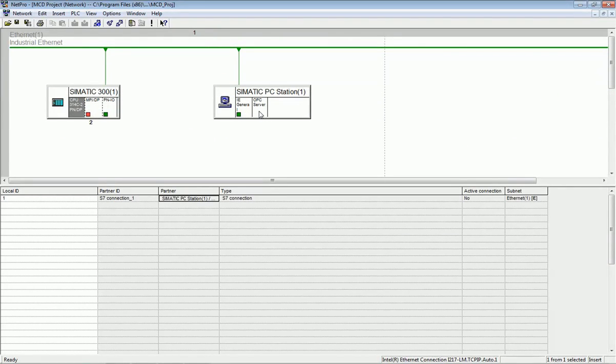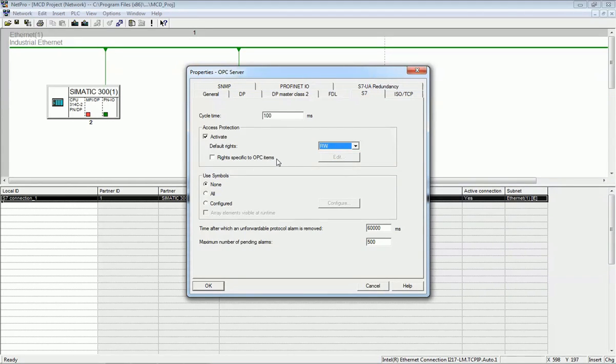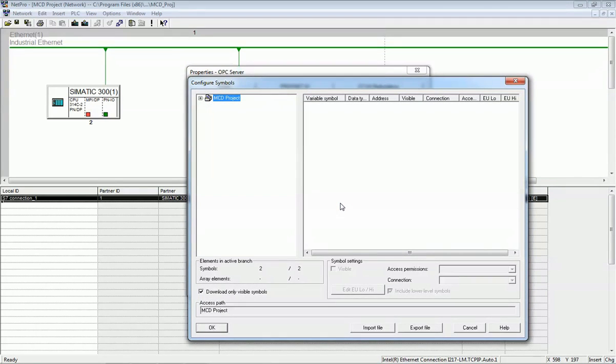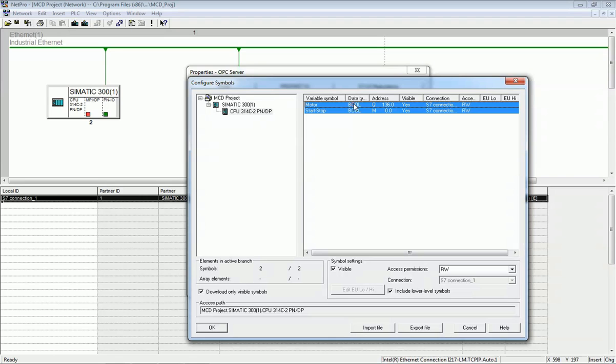There are no errors. Now we go to the PC station, right-click on the OPC server and go to Object Properties. Here we have the S7 option — we set it to active and select Read and Write for both options. Then we click Configure, open the PLC, and we get the variable symbols from the programming. We can see two variable symbols — Motor and Start/Stop bit. We add them to the OPC server, click OK, and then download.